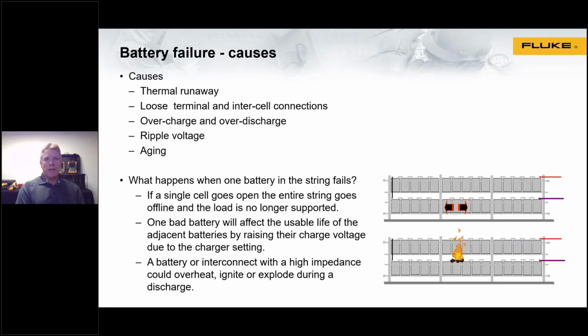As we mentioned, if you have a string of batteries all connected together, what happens? If a single cell or a single jar goes open, the entire string goes offline. So again, it can have a huge impact. And one bad battery will affect the usable life of the rest of the string. It'll raise the charge voltage and shorten the life of all the batteries that are in the string.